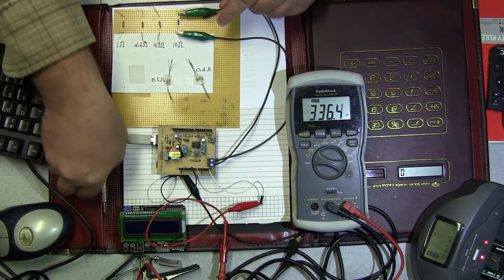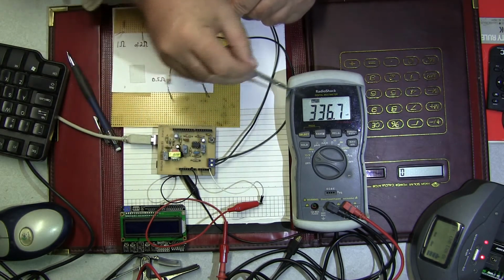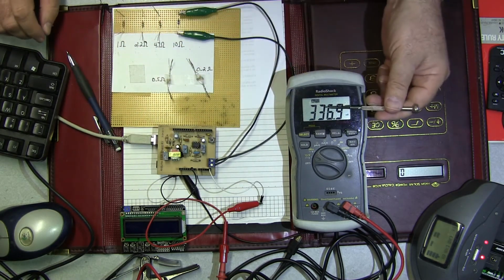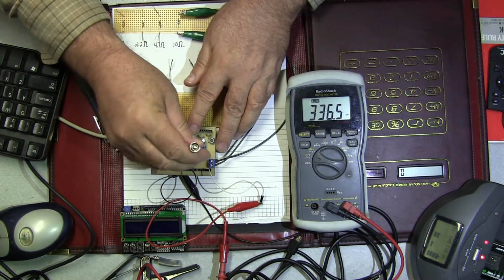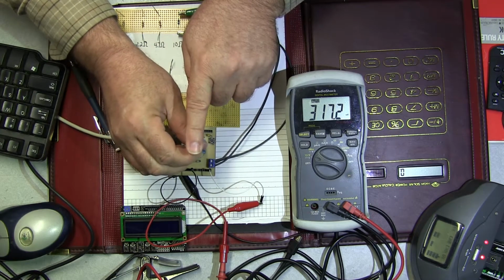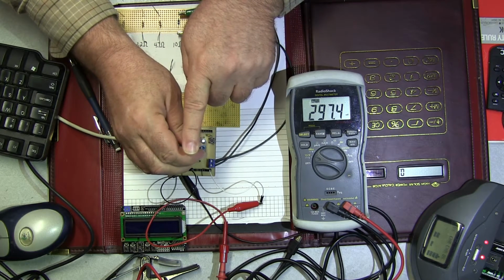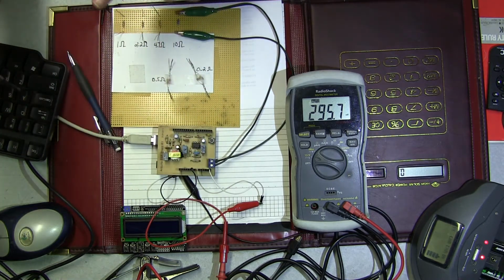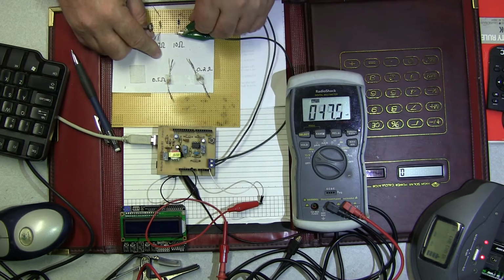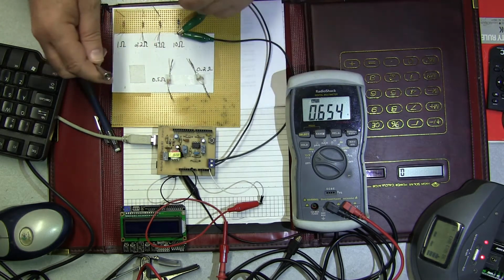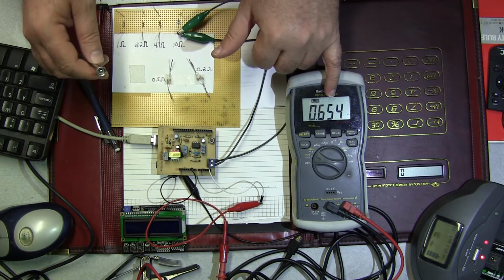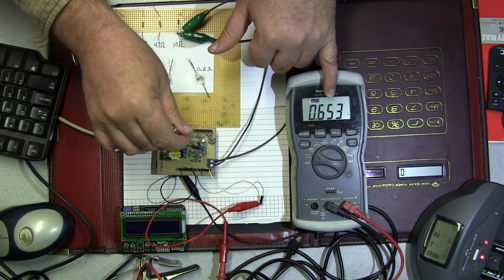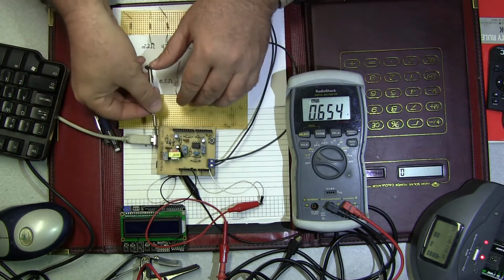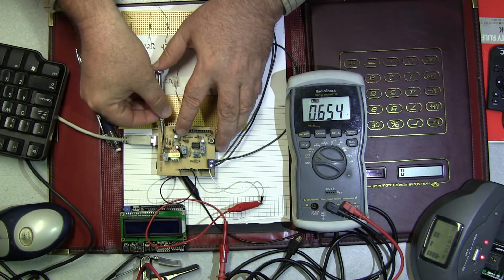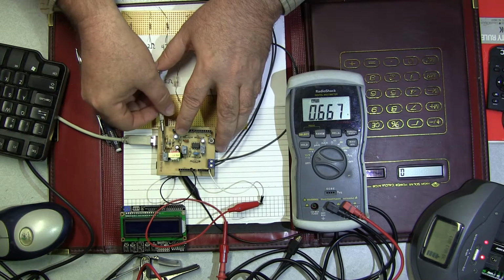And what we need to do now is on the attenuation pot, the attenuation of our leads, we need to turn the attenuation down until we have a reading of 295 millivolts. Okay, there's 295.7. Now we'll go back and we'll short our leads out again. And you can see that reading has dropped because the attenuation changed on our probes. So what we need to do is just go back and forth on these pots until we get it spanned out to read 700 at the top and 295 at the bottom. And it doesn't usually take very long to do it.